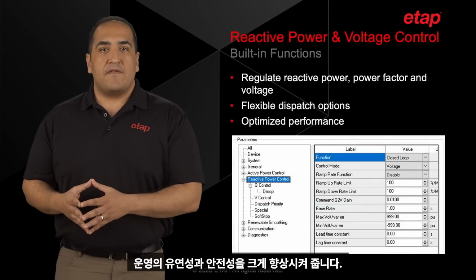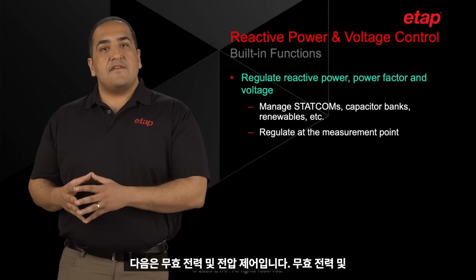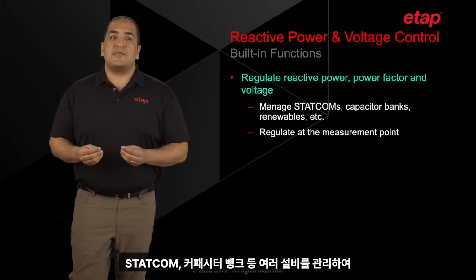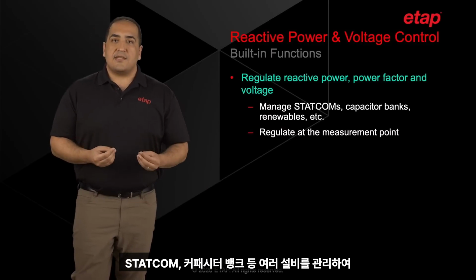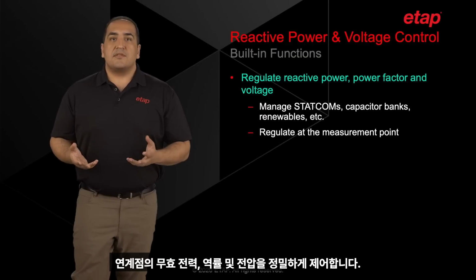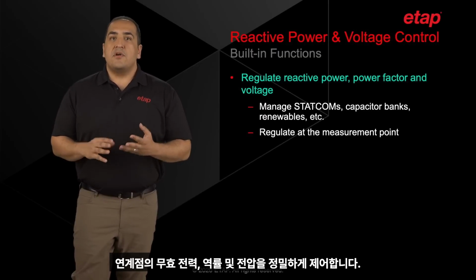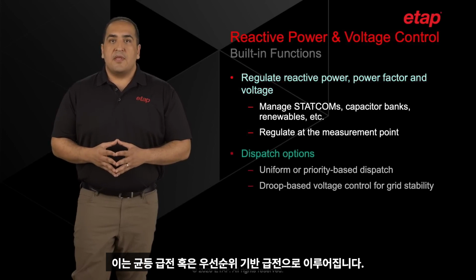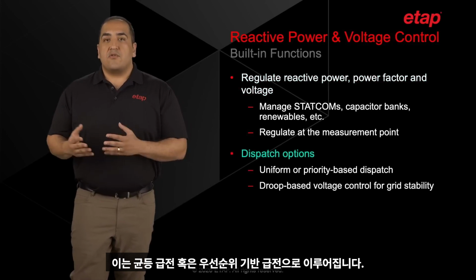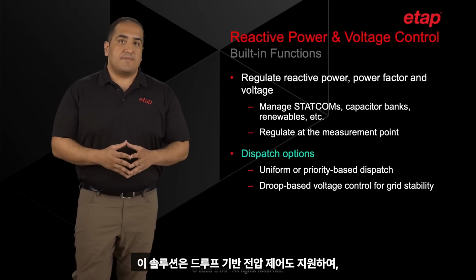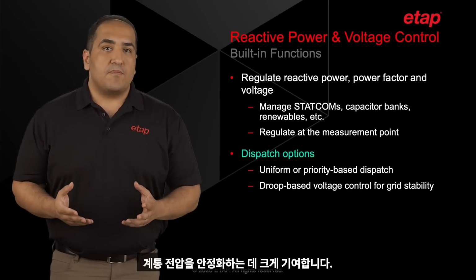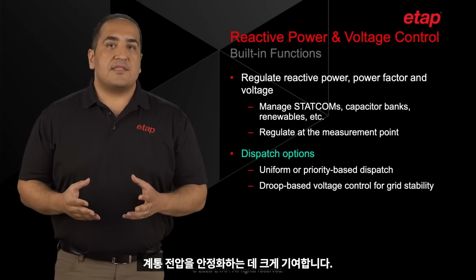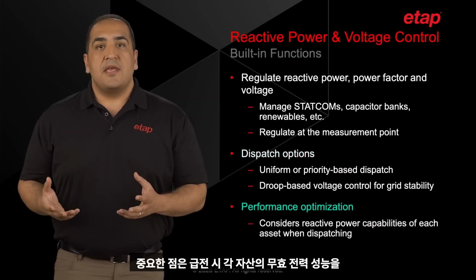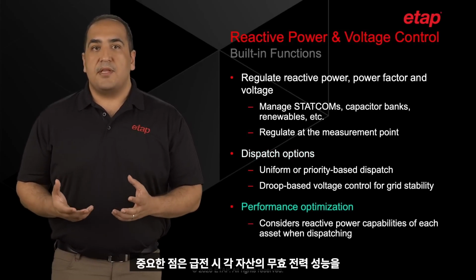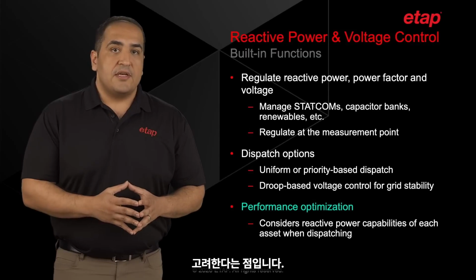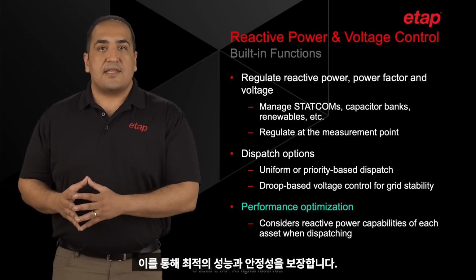Next, we have reactive power and voltage control. In the reactive power and voltage control loop, ePPC manages various resources such as STATCOMs, capacitor banks, and renewables to regulate reactive power, power factor, and voltage at the point of measurement. This regulation is achieved through either uniform dispatch or priority-based dispatch. The solution also supports droop-based voltage control, which helps stabilize the grid voltage. Importantly, ePPC considers the reactive power capabilities of each asset during dispatch, ensuring optimal performance and stability.